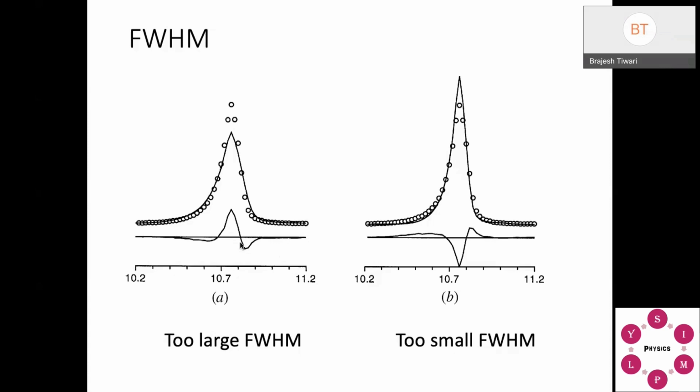The anisotropic thermal parameter will be controlled from the atomic position, where it's written B1, B2, B3, or B is given. Now if that parameter is not fitted well, you are going to get this type of behavior. Or it can be the other way around. So either the total thermal parameter you should try to change, or that can be another trouble. Once you zoom in, you can judge which parameter you should change. So how to decide it?